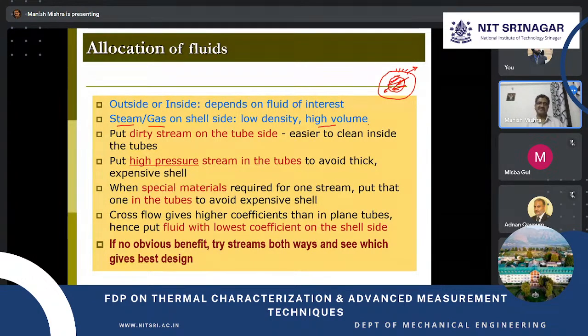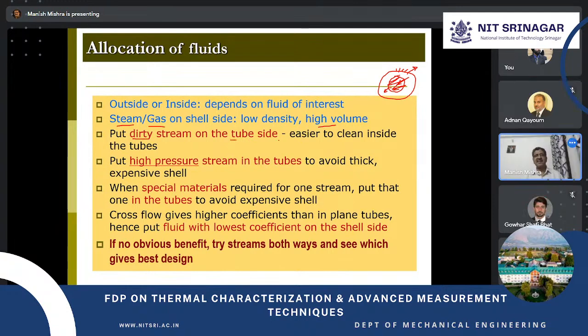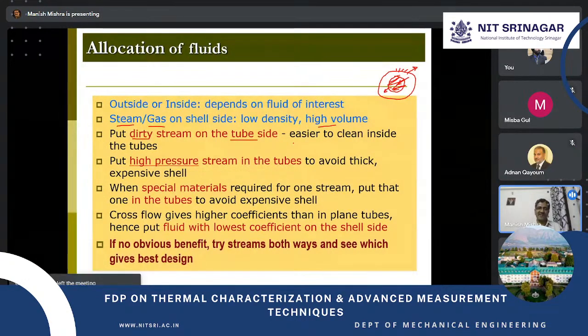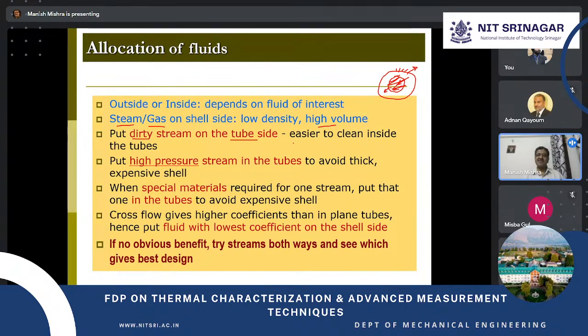Now suppose I have a dirty fluid stream, maybe coming from some part of a chemical process industry. In that case, I should put it on the tube side. Why? Because cleaning is always a problem. Apart from fouling, if contaminants are in the fluid, they will get deposited, affecting heat transfer, and there may even be clogging or choking after some time. So to avoid that, if it is on the tube side, tube cleaning is always easier. You still need to clean periodically, but it's easier compared to shell side cleaning.